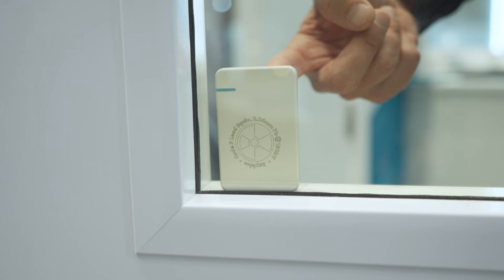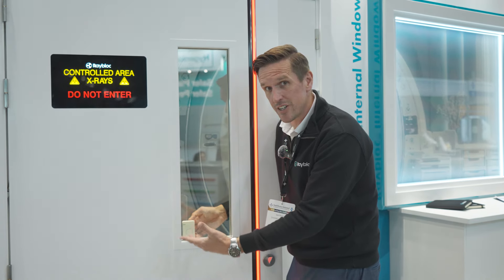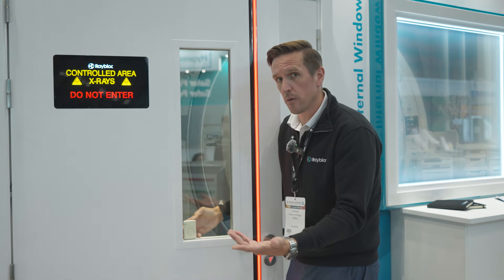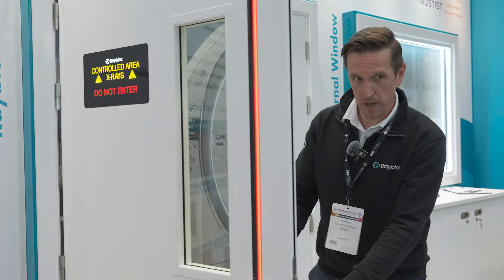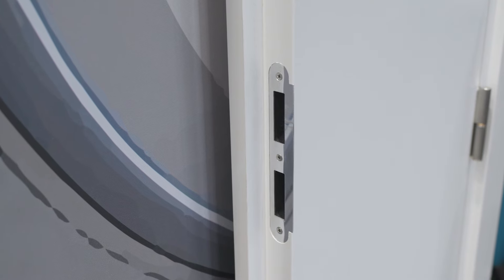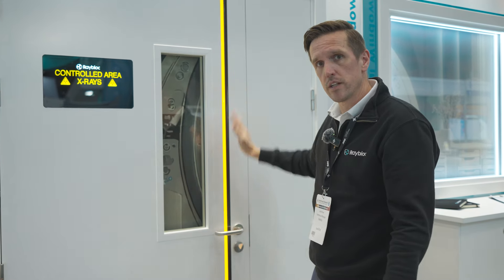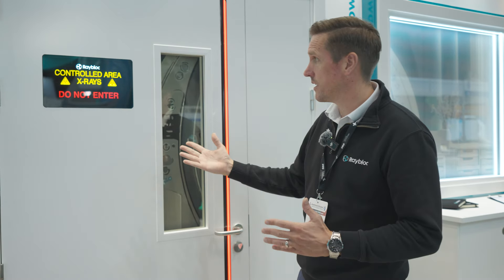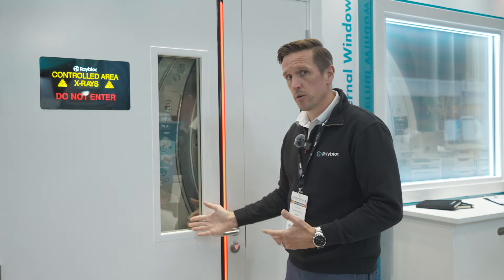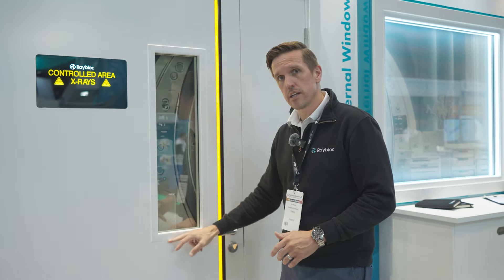Vision panels are available where needed. We've got etching on the glass showing Code 5, the thickness of the glass, and the energy level — it's an RPA's dream to have that information readily available during critical exams. We're also bringing the rebated meeting stile: a nice PVC wrap door with lead integrated within the rebate itself, doing away where possible with the Astragal for a smooth-looking door. Available in PVC laminates, veneers, different finishes, sizes, privacy glass, interstitial blinds, laser blinds, and beaded vision panels with flush-mounted availability.